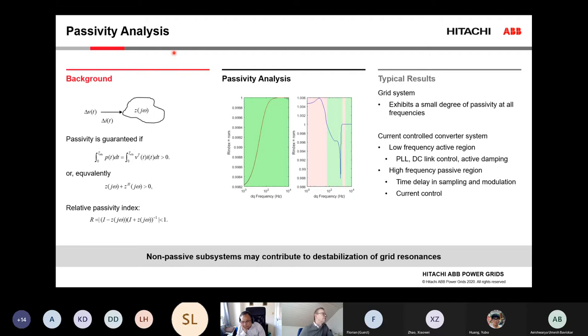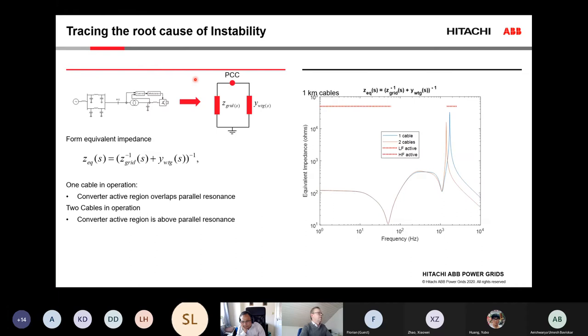So the second, okay, we can look here now, actually explaining what went wrong in the previous example, and explain that using the concept of passivity. So here is our test network again. We have computed here an impedance equivalent of the grid and an admittance equivalent of the converter system. And if I know those two, I can just calculate the parallel equivalent impedance seen from the PCC. So I can invert my admittance matrix, sum it with the impedance matrix, and then invert again, and I get an equivalent impedance. And this is what you see here to the right plotted with the two curves.